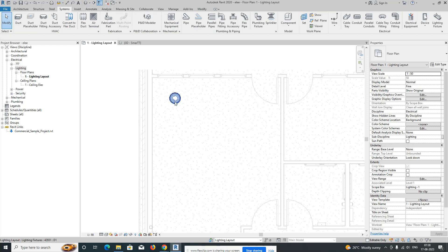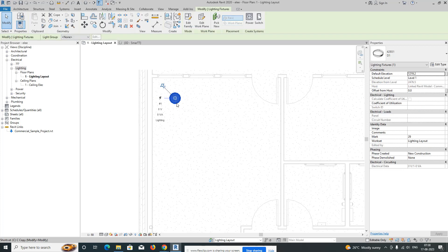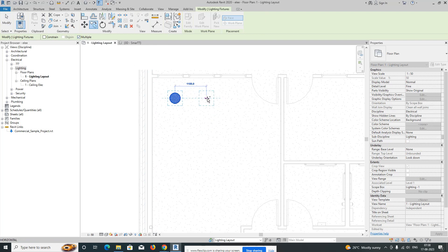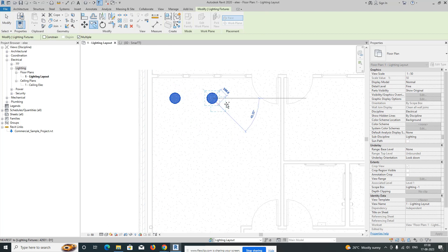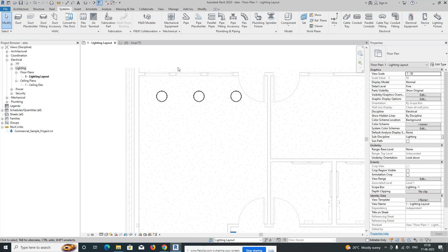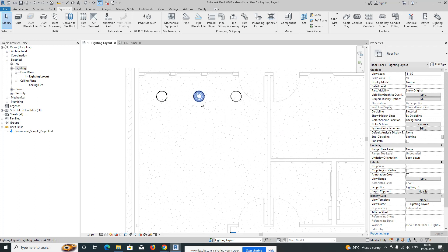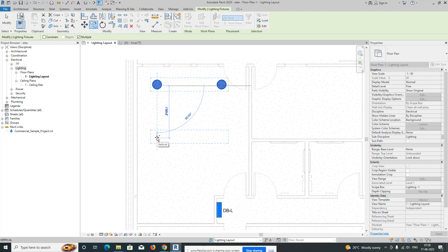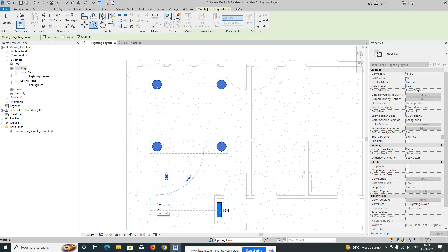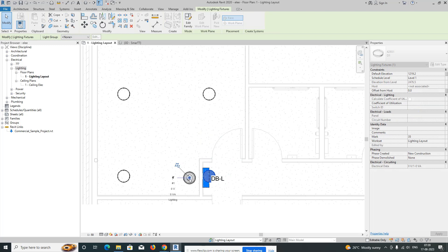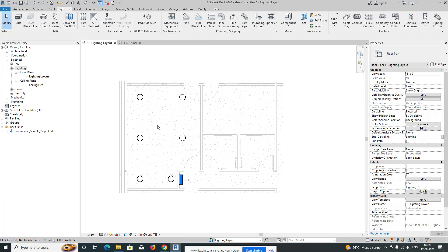Once you fix the dimensions, copy the light by choosing Multiple. Pick the point — I need to place one light around 1300, then the next light also around 1300. Three lights are fixed. If you're not comfortable, you can change the dimensions. If you need only two lights, delete one and copy again. I'm giving 2500 spacing, and here also 2500.